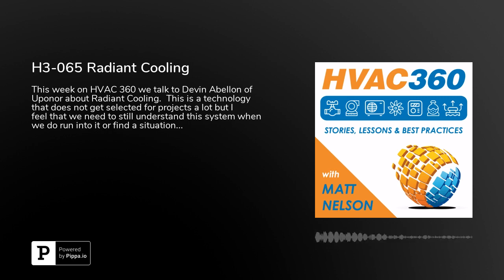Yeah, there are a couple of different ways to do it. Many of the radiant cooling systems that we see are actually combination heating and cooling systems, so you're using the same series of tubes for both heating and cooling, which adds a little bit of complexity. So you're right, essentially we've got a thermostat, a room temperature sensor that's monitoring how far we are from set point. Typically, we'll also have a slab temperature sensor so we can monitor the slab temp. Usually that's used for high-low limit control, so the slab doesn't get too hot or too cold.